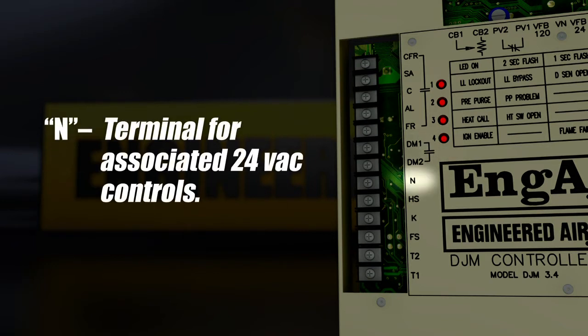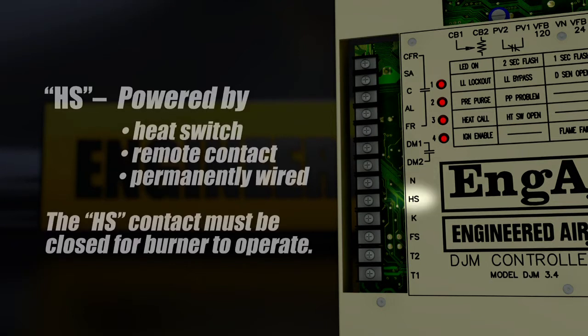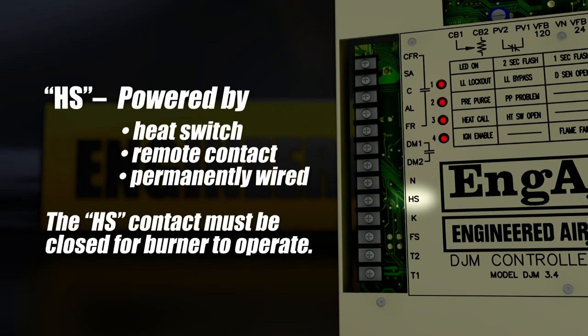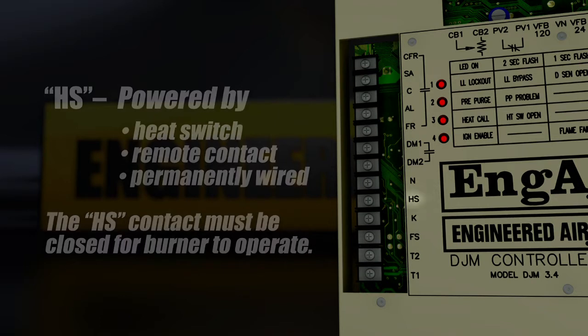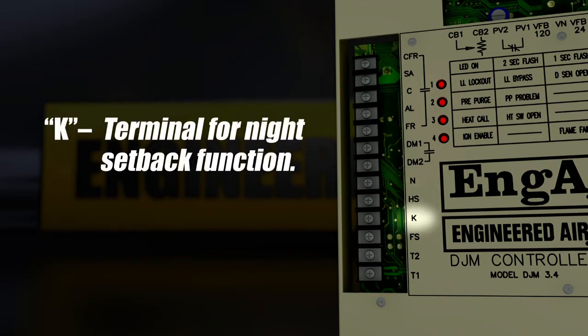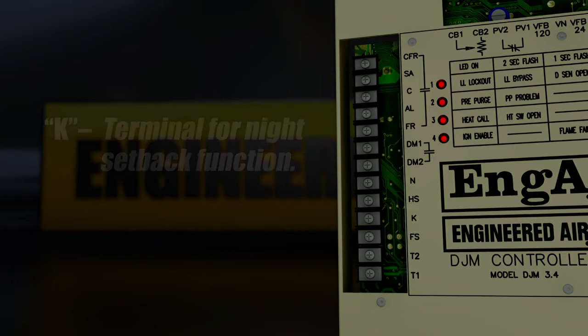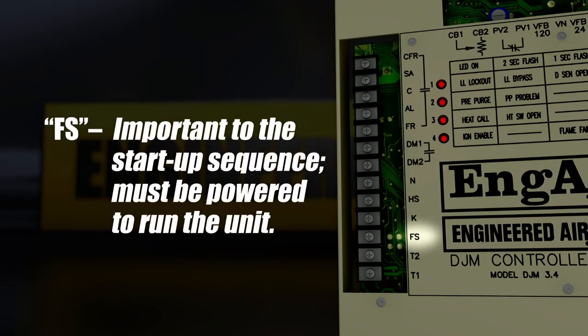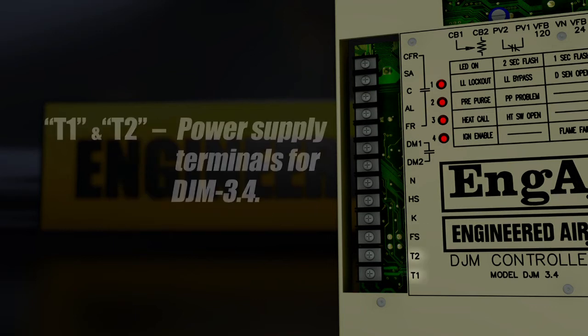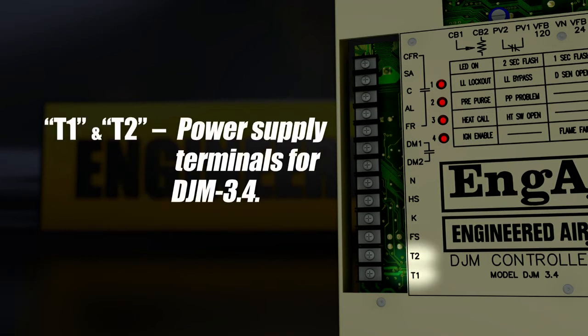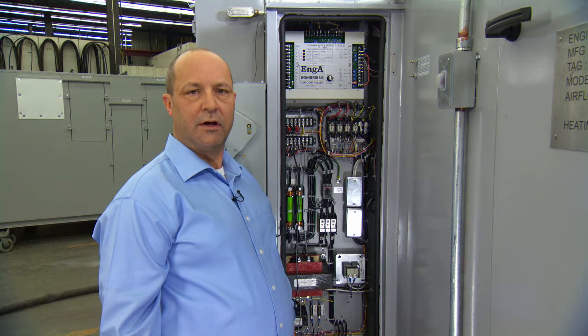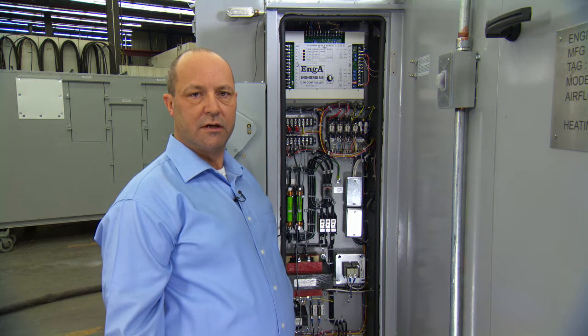N is our neutral connection from the 24-volt supply. HS is the heat switch to allow the heat to operate. K enables night mode. FS is the fan switch to enable operation. T1 and T2 are the 24-volt supply power to the board. So now we'll be examining the external controls, right side.